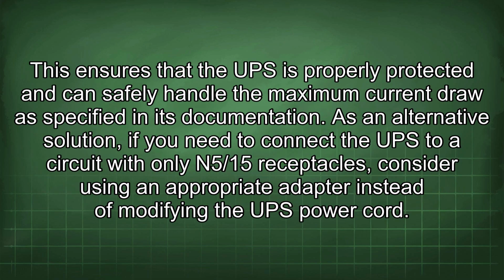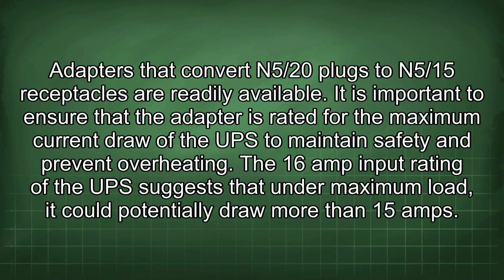This ensures that the UPS is properly protected and can safely handle the maximum current draw as specified in its documentation. As an alternative solution, if you need to connect the UPS to a circuit with only N5/15 receptacles, consider using an appropriate adapter instead of modifying the UPS power cord. Adapters that convert N5/20 plugs to N5/15 receptacles are readily available.